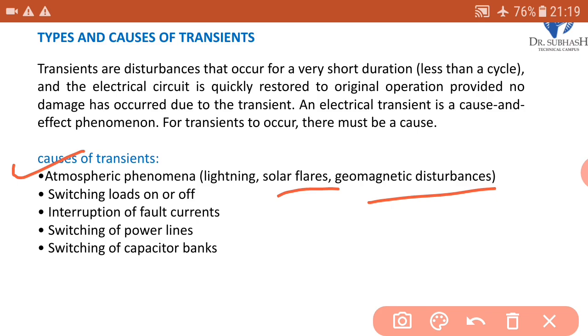Switching loads on or off. This is also a cause of transients. Due to switching loads, a transient may be generated. Another cause is interruption of fault currents. For example, due to the operation of a circuit breaker, there is an interruption of fault current, and due to this a transient may be generated. Next cause is switching of power lines. During power line switching, a transient may be generated in the system.